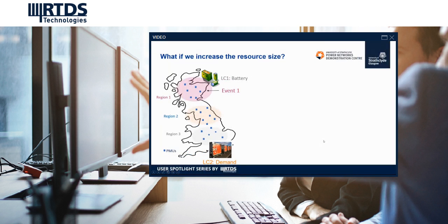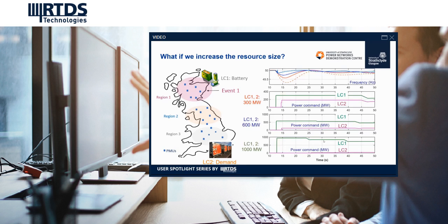Now let's have a look at what happens if we increase the resource size on both sides with the same event. So we have 3 cases here: 300 megawatt, 600 megawatt, and then 1 gigawatt. You can see here, the first plot is the same as the previous case. Basically, local controller 1 deployed 300 megawatt.